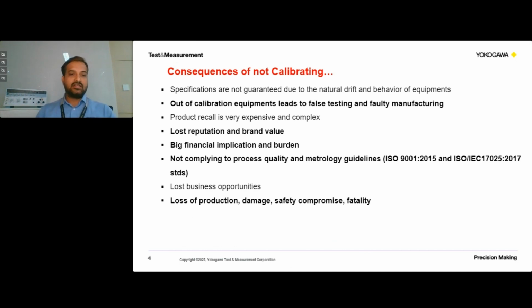And loss of production, damage, safety compromise and fatality. If you are considering calibration of instruments for a process industry, and an instrument has an erratic reading because it is not calibrated on time, it may lead to damage of the entire process plant, like a boiler blast or a burst of the pipeline. So those kinds of consequences may also be faced.